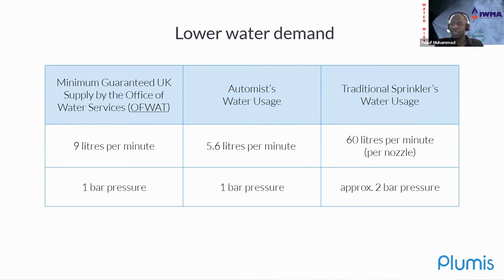So they guarantee in residential and domestic buildings that they will provide you 9 litres of water per minute at a single bar pressure. That is their obligation, whether it is Thames Water or Severn Water, whoever your water provider is. And Automist offers a unique attribute because we were only drawing 5.6 litres when we activate at a single bar. So under that threshold, whereas with a traditional sprinkler, you're going to need significantly more, which means typically you either need a commercial water feed, an upgrade to your existing supply, or a tank.